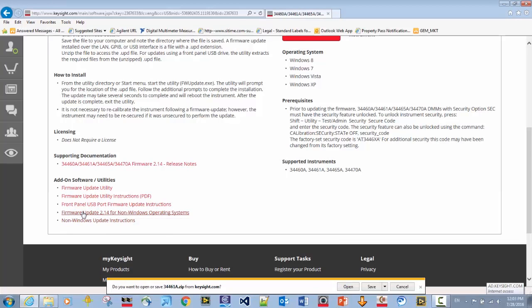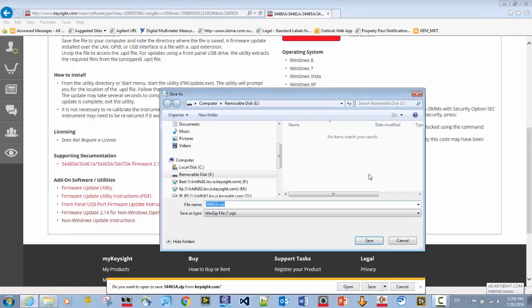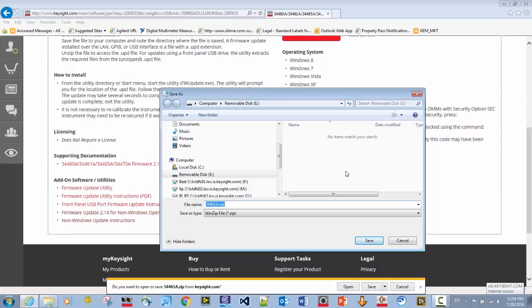So I select that link, which brings up a window below asking me where to save the file. I don't want to open it. I want to do a save as, because what I want to do is save it to a USB thumb drive, because it is the thumb drive that will be transferred from the PC once the files are there onto the instrument, and then the firmware using some front panel keystrokes will update the firmware.